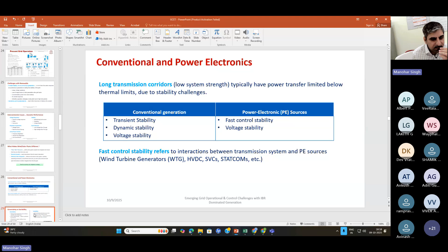When we are more dependent on these resources, like solar, it's not only that they are variable—all of a sudden when the sun goes down in the evening, their generation immediately falls. We lose around 30% generation within half an hour in the evening, and 30% generation within half an hour in the morning. So for a very short span of time, I must have some resource which can compensate for the down ramp rate and up ramp rate of these devices.